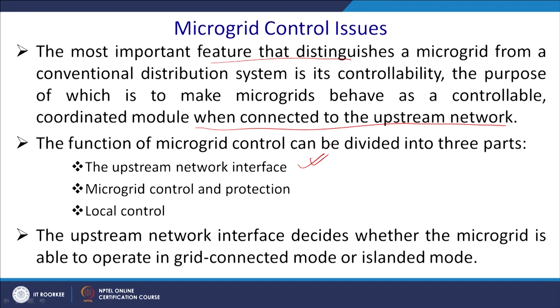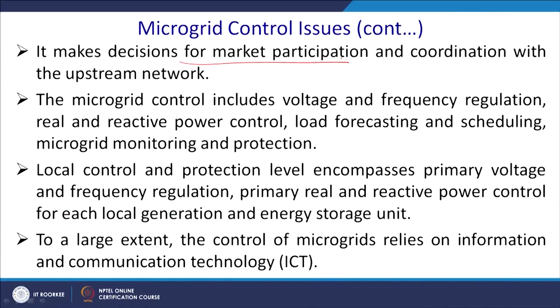The upstream network interface decides whether the microgrid is able to operate in grid-connected or islanding mode. Many solar inverters in India, when connected to the grid, dispatch power to the grid, but if power goes off suddenly, they have to stop and cannot feed local power. So one key capability a microgrid should have is that in islanding mode, it should be able to feed the local load. It also makes decisions for market participation — whether to sell power to the main grid — and coordination with the upstream network regarding power quality.